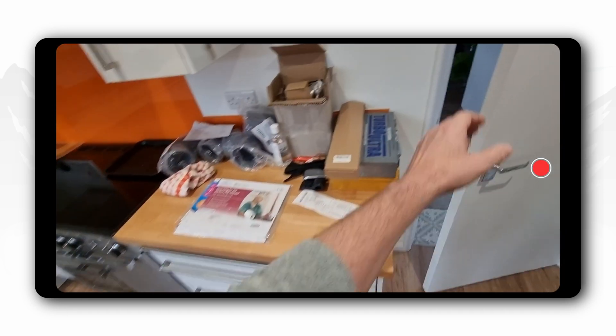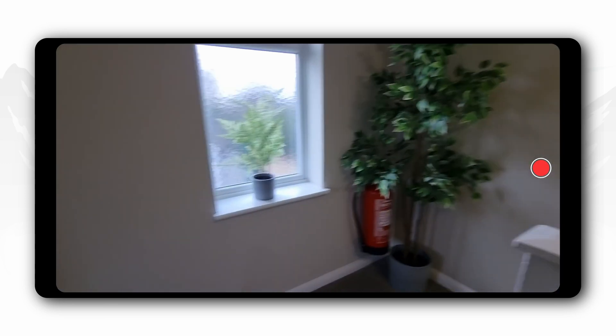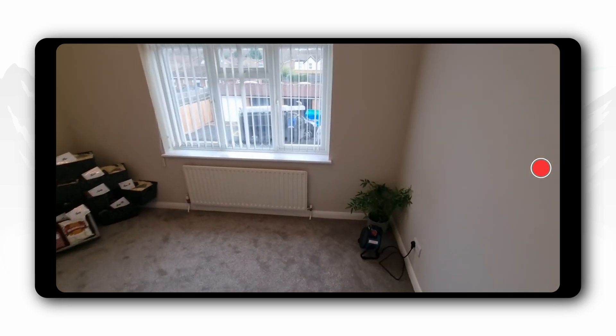So it heats this area — normal double glazing, normal back door, just a normal house. Nothing special about it, not new build by any means, let's say 1960s. There's no radiator in this hallway. This is essentially like a flat here. No radiator in here, which you would normally probably upgrade if you're going to have a heat pump. This radiator in here is a single panel, single convector — not even a double. And as you can see, it's not even as wide as a window. You'd normally match it to the window even when doing just a normal gas boiler.